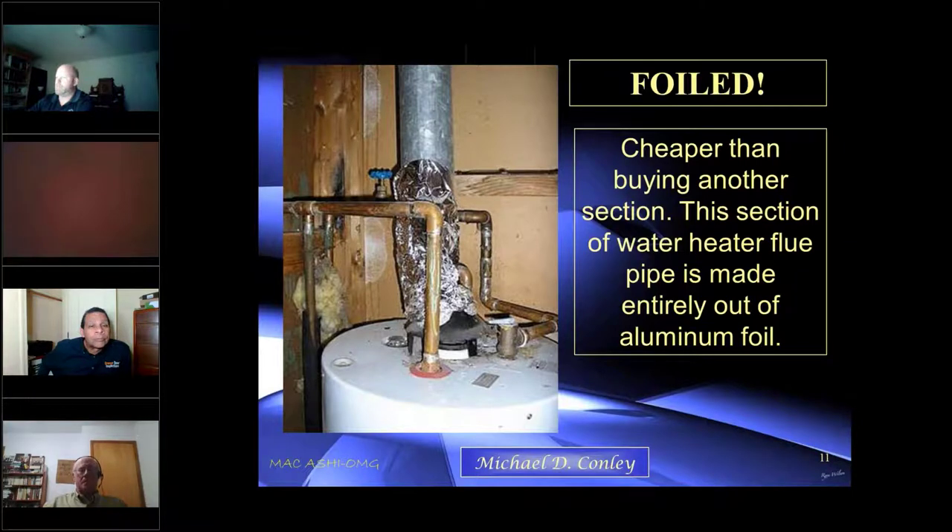There's a limit on the number of bends you can have — I think it's a maximum of four or five. We have one, two, three, four here. Can't see where it goes from here, but if it goes out anywhere that's five, and that's way too many.